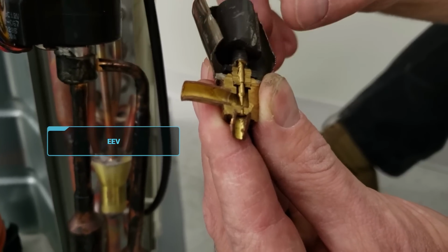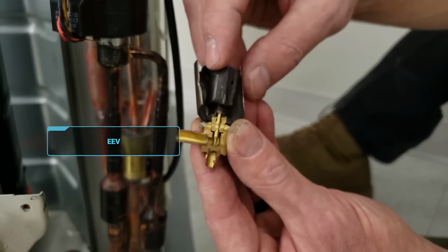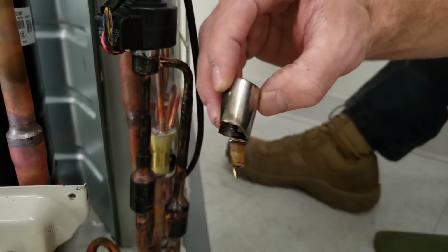Another thing is if you see that the line is severely frosted or iced over, it's most likely undercharged, or it could be other things as well. Like a thermistor is telling the system that it's reading an incorrect temperature, or you could even have the EEV maybe has rust between the head and the stainless steel shell, and the magnetic field is not really getting to the inner permanent magnet within the EEV, and it's not able to open up more. So it could be multiple things. You can't just blame it on the refrigerant charge. Now, while it's running, if you measure maybe a total superheat of 30 degrees or 40 degrees, well, then, once again, you think it's low on refrigerant, but it could be some of these other electrical devices. So that's what you can do.